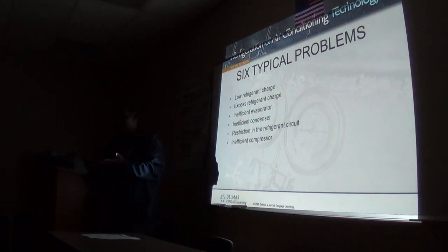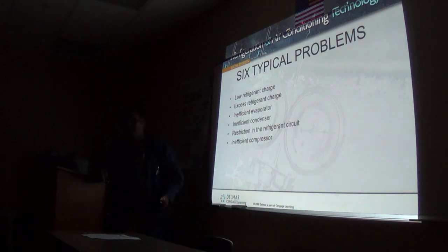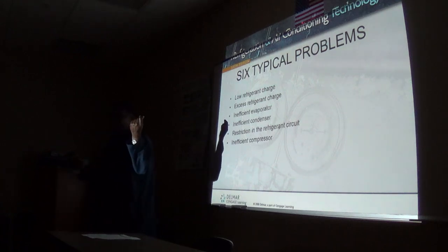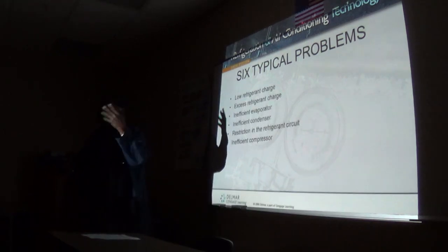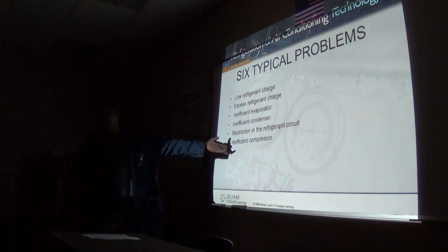So, an inefficient compressor, if it's the valves, you definitely will know at some point when the pressures equalize. One of the things you can do is shut off the system, turn off the switch, and look at the gauges. If your gauges begin to equalize like that, you know that you have a problem with that compressor. It's not supposed to jump and equalize. It's supposed to take roughly 2 minutes for those pressures to equalize. But if it does a Usain Bolt thing, change your compressor. You don't even think about it.